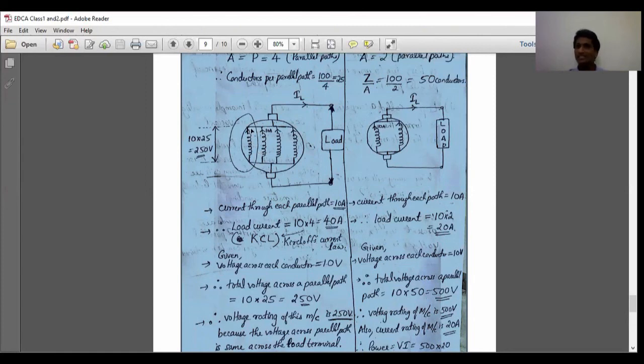That current is the circulating current, which is not useful for our machine. Clear? Theoretically, these 2 points should have the same voltage, but unfortunately, due to some voltage drop, there is a slight voltage difference. So there will be a current flowing within the circuit. That is called a circulating current, which is not useful for the machine, and it will create more heat loss.